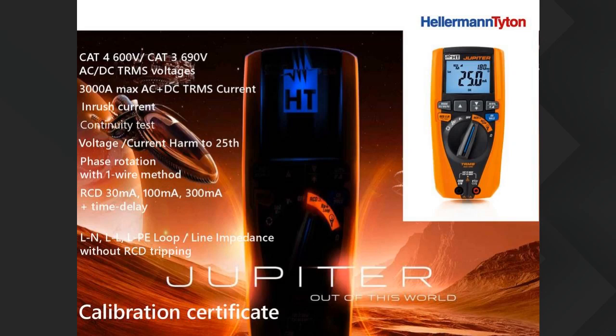So if you go through the pointers that I've got there, first of all, it's a Cat4 600 volt meter or a Cat3 690 volt, depending on the voltage systems that you're working on. It's got AC/DC TRMS voltages. It can measure up to 3000 amp maximum. That is through a specific flexible CT that you can buy for the meter as an optional extra. Then it can measure inrush currents, it can measure continuity, it can measure voltage harmonics as well as current harmonics up to the 25th. It can do phase rotation with a one-wire method.